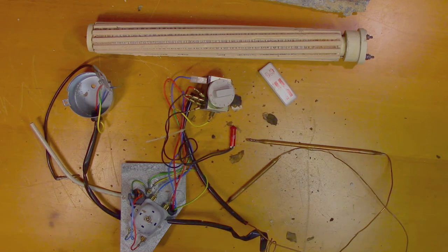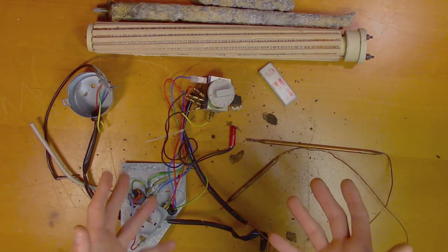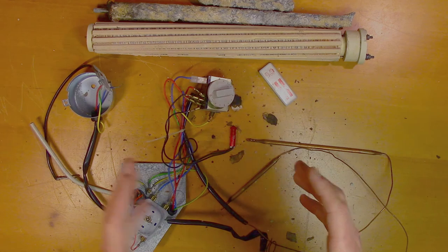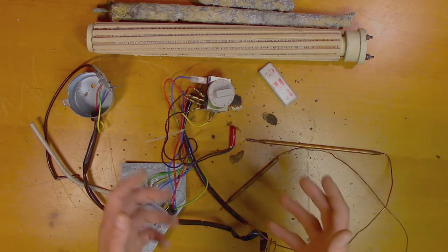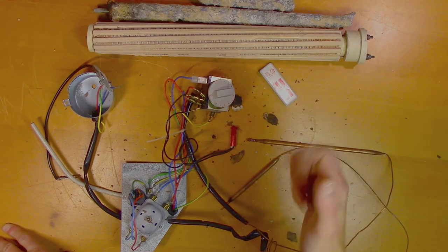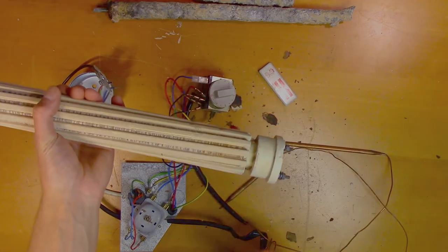So what ultimately caused it to fail was that the barrel had started to rust and it started to leak. Water that leaked out was running down to the lowest point of the barrel which is where you find the heating element connectors.